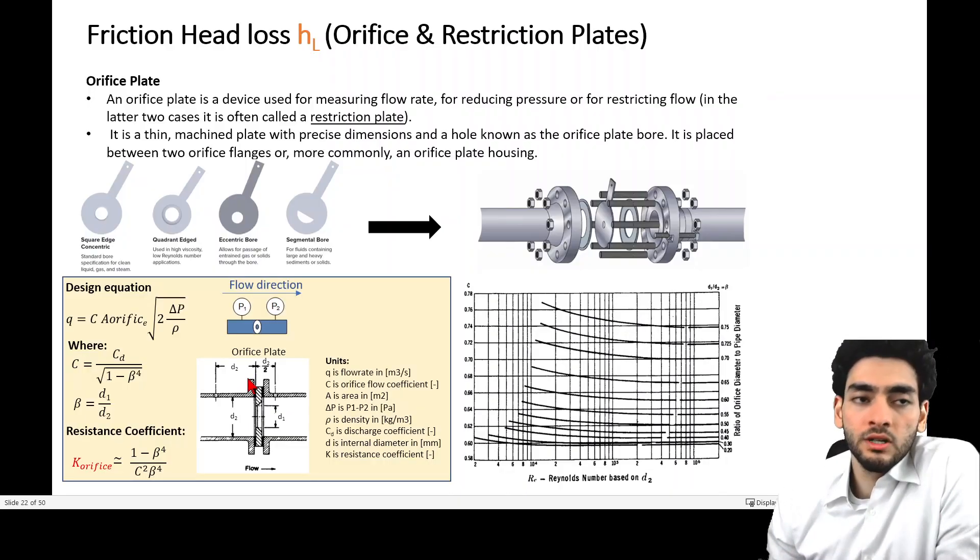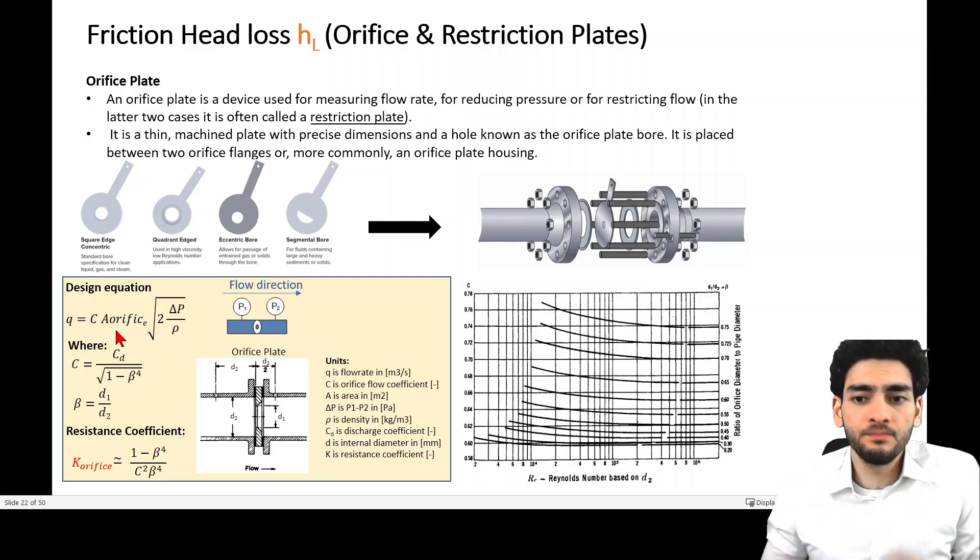According to the Crane handbook, the flow rate that passes through the orifice is equal to an orifice flow coefficient C multiplied by the area of the orifice A, multiplied by the square root of 2g times delta P over rho, all divided by the square root of 1 minus beta to the power of 4.